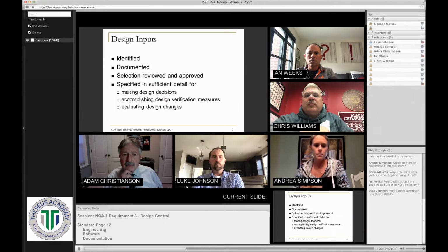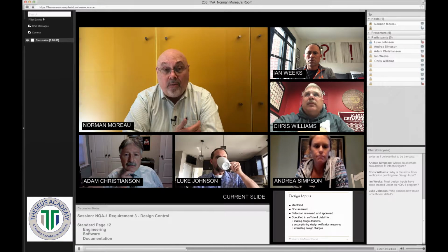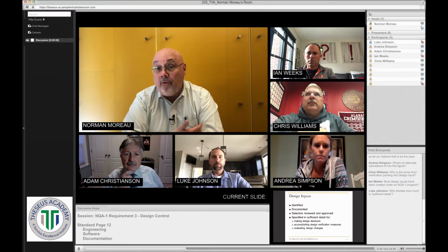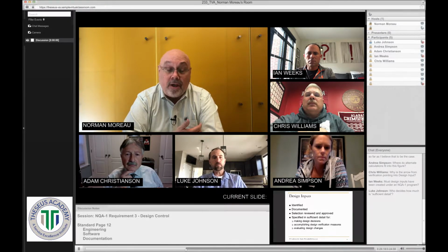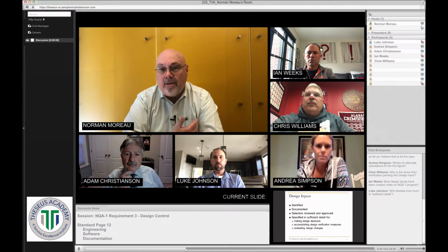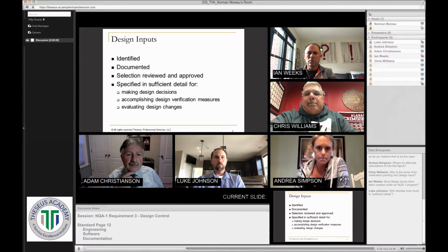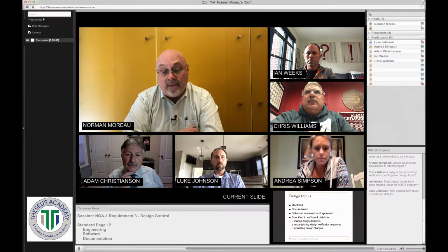The next slide is about design inputs, and there's very specific requirements. Identified, documented. How did we select them? Someone has to review and approve those inputs. Think of things like temperature, humidities, the environment, research papers that are done to support the practice, and then specified in sufficient detail.